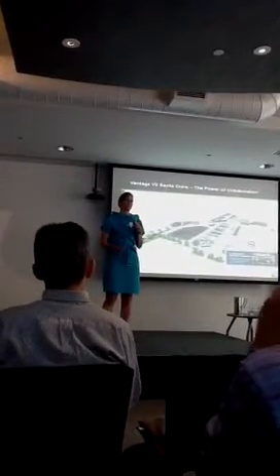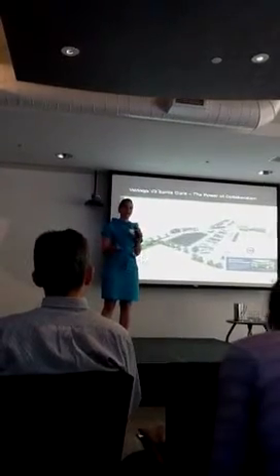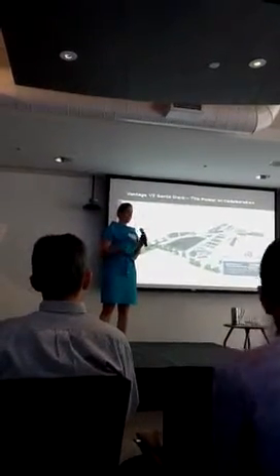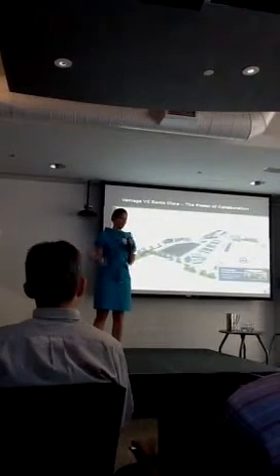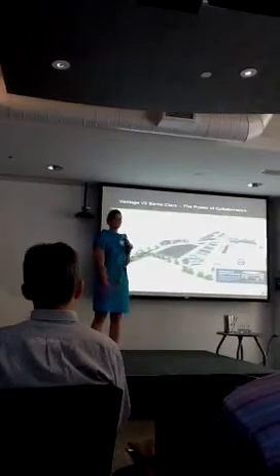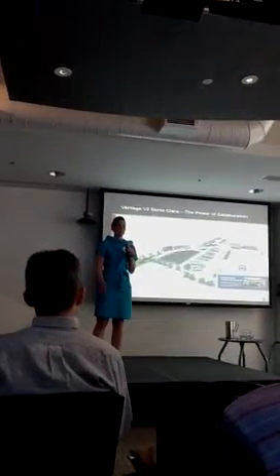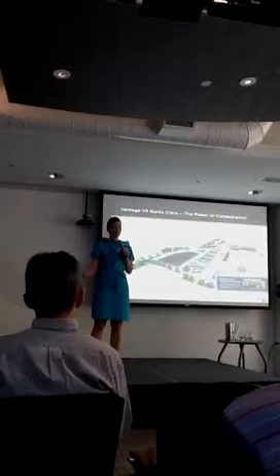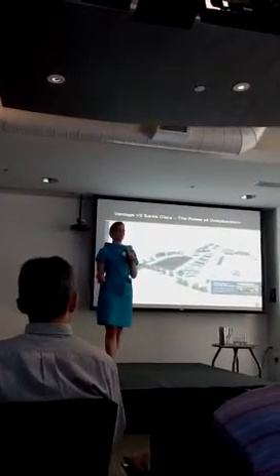What we're doing is we're trying to find effective ways of utilizing the environment that we're in. And these environments differ. So in California, yeah, bringing outside air in is excellent. In other climates, Pacific Northwest, where you have some arid climates, indirect outside air economization, amazingly successful. You can use it 100% of the year, have no chillers. And you can get really high densities just by moving large volumes of air.